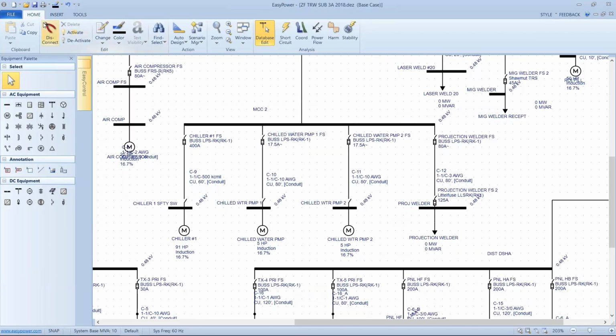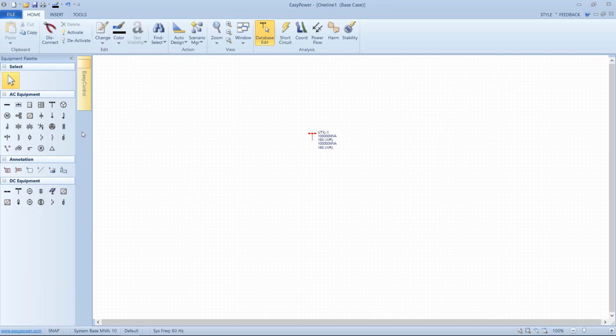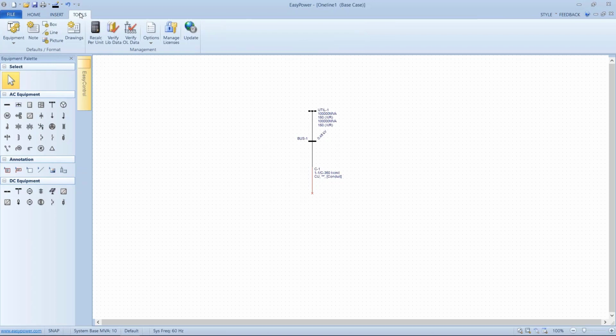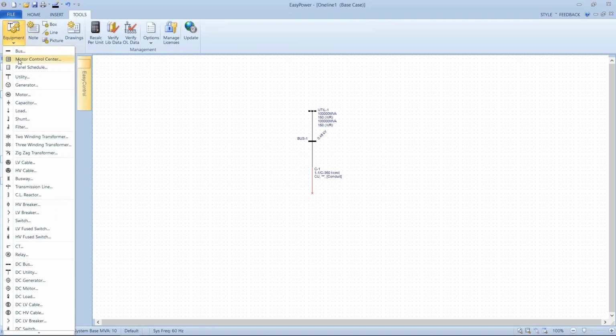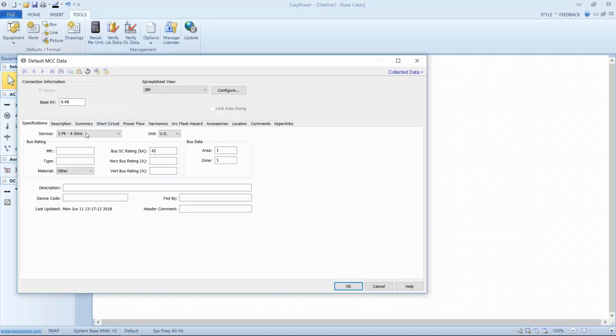So what we're talking about is a couple things. Let's start with a new one-line diagram, and just set up my motor control center. Let's say we're going to be working on 480 volt buses. Now, if I go to the tools tab here at the top, down to equipment, and I select motor control center, if I know I'm going to use several motor control centers that have all the same manufacturer, I might want to enter that data here. So let's say we're using Square D. I think it was a Model 6 that we were talking about. I really did want to capitalize it.